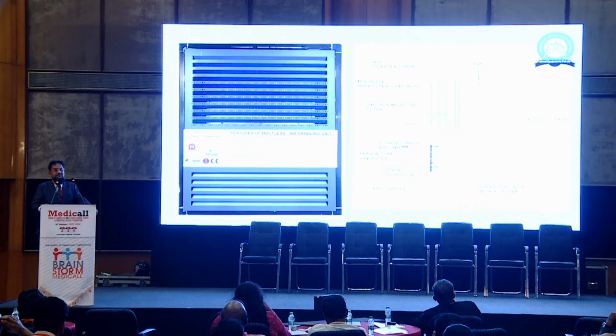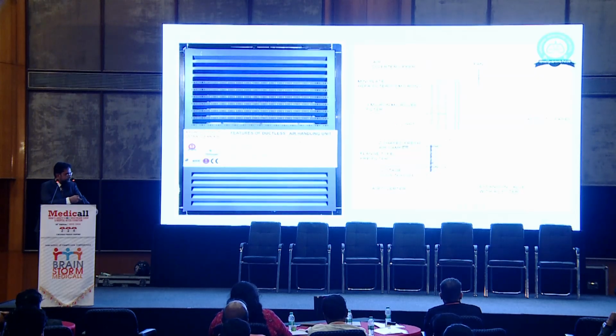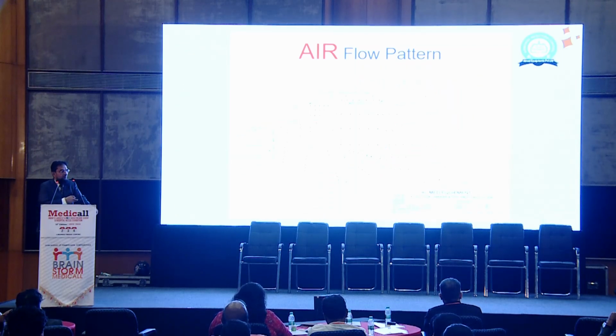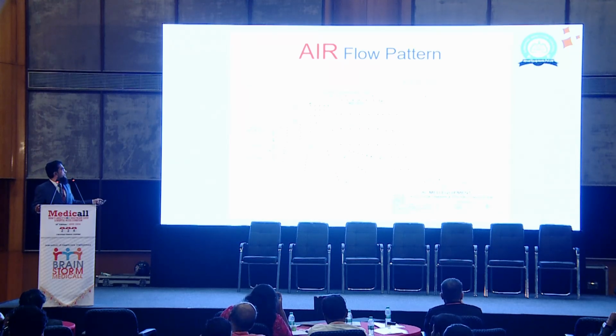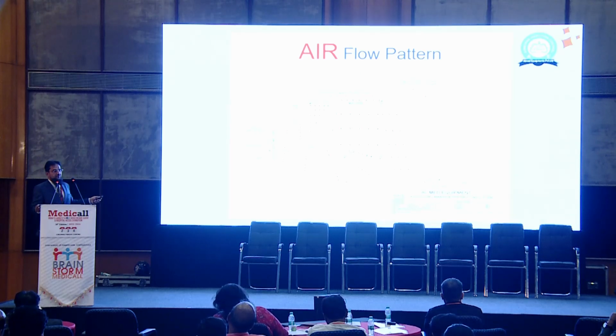Where height is a concern, we have wall-mounted AHUs also. You can put the wall-mounted systems where the challenges are with heights. As we had given earlier, we are using guided airflow technology for making the operation theaters. Air goes to the HEPA and is supplied from the upper side, going to the ceiling side. Here is the backward curve fan, and from this HEPA it comes down at the table level. This type of air circulation is the guided airflow technology we had given earlier.